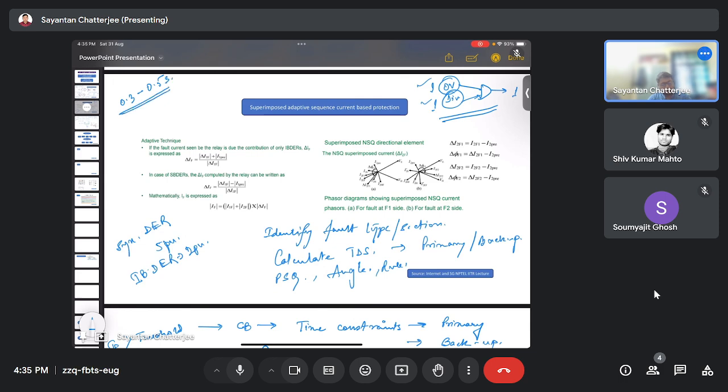We always have to take into calculation that this CTI value should be less than 0.3 to 0.5, meaning within 0.3 to 0.5. There are some rules for the grid codes that they should always be a part of these values. So accordingly, we can play with the design part.